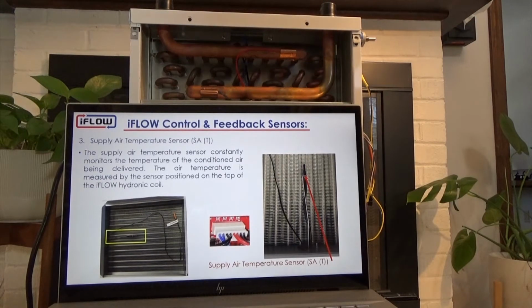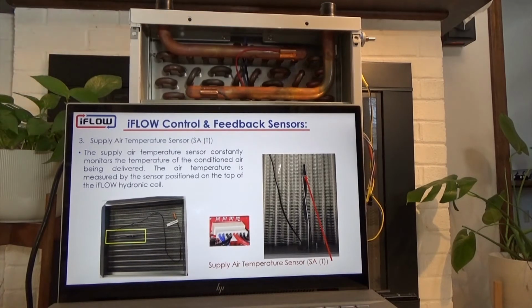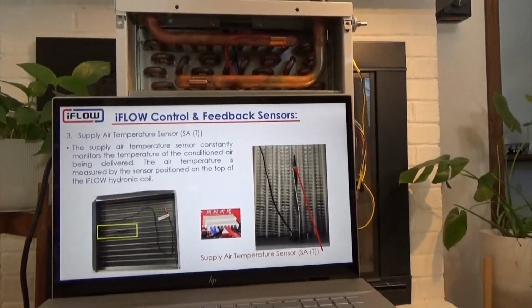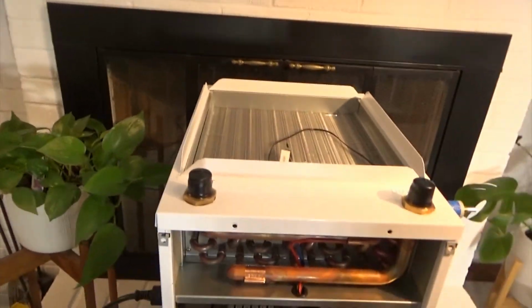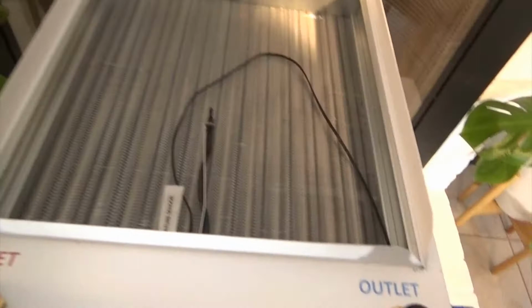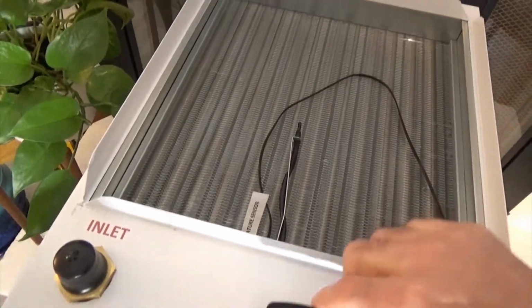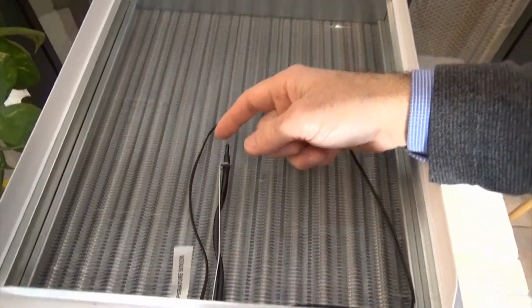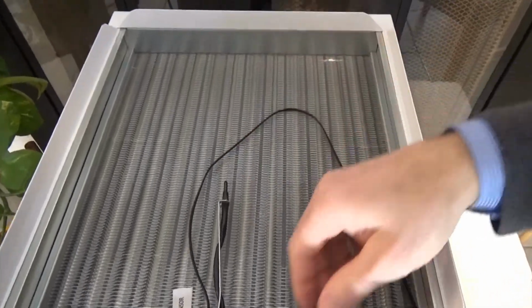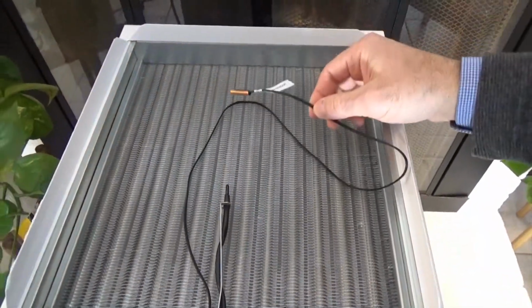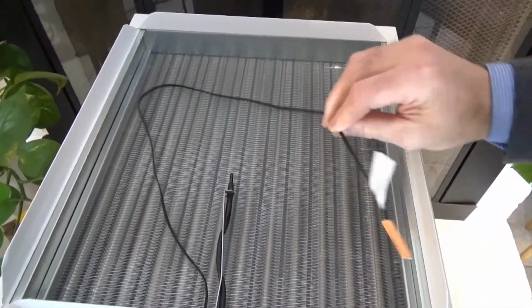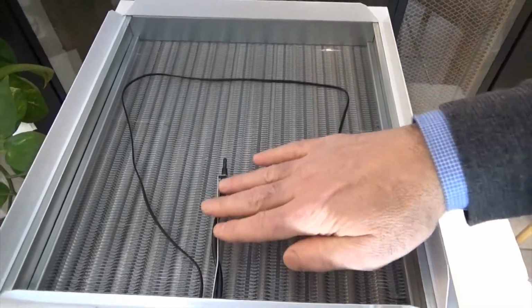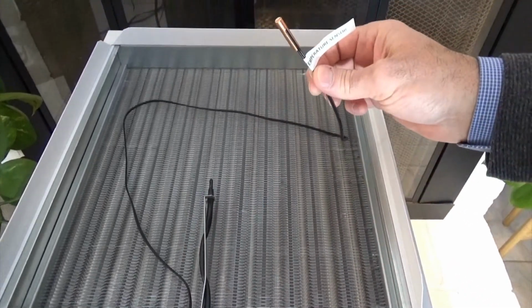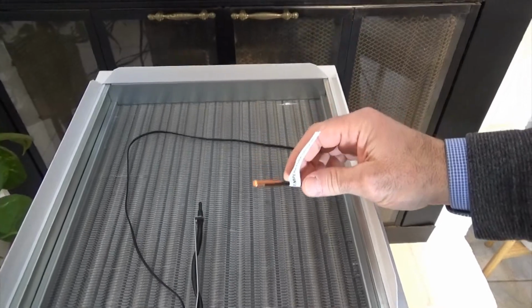The supply air temperature sensor is located on the top of the coil, and I can give you a little bit of a visual. If we come up to the top of the coil, you can see this is the supply air temperature sensor, and then the evaporator temperature sensor. When you open the unit, that's what you're going to see. This is already prefixed. This will strap to the top of the evaporator coil.